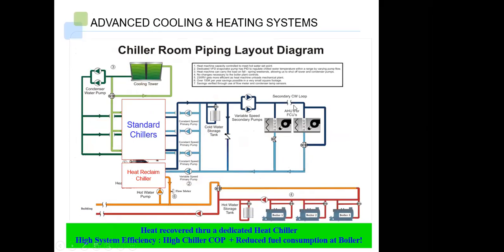So while it cools part of the chilled water system, on the second side it doesn't reject its heat to the cooling tower. It supplies that high temperature hot water, which is typically around 45 to 50 or 55 degrees depending upon the need, to the boiler cycle. So what happens when this chiller is providing the heat, we need not fire the boilers until the load of the heating plant or the boiler hot water requirement is much higher than what this heat reclaim chiller can produce. So it significantly saves energy.